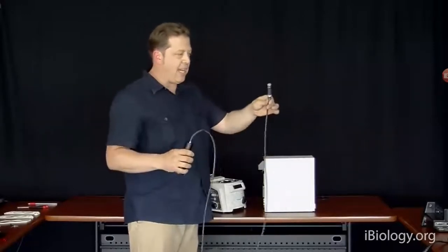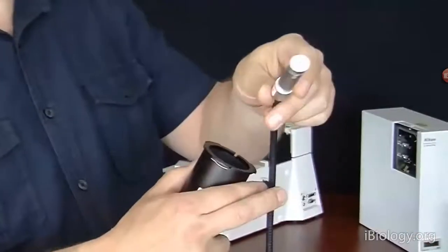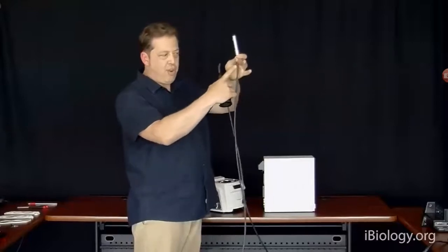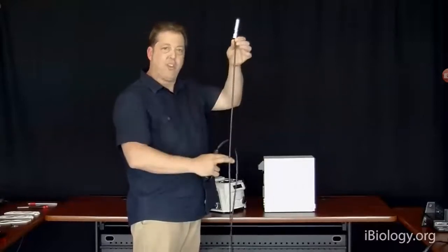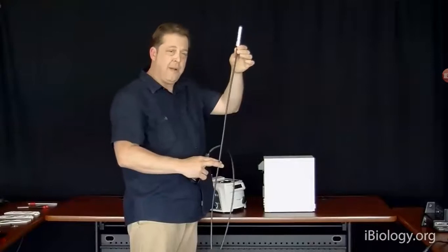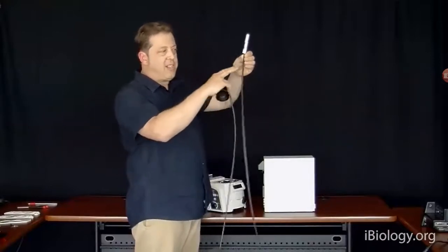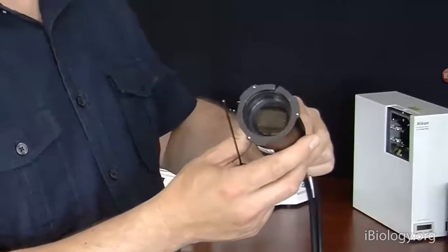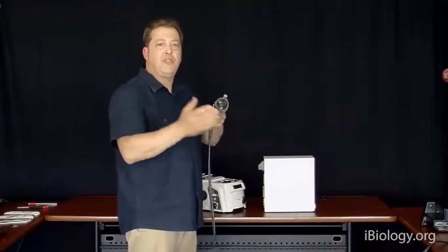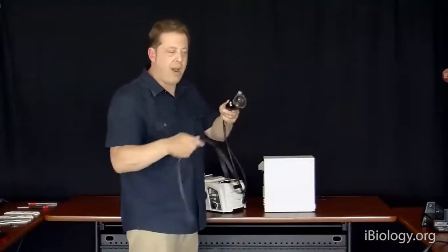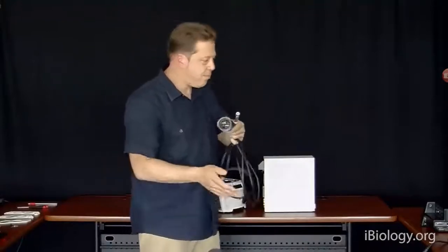And all the light goes in through what's called a liquid light guide. So the light coming into this aperture is actually trapped through total internal reflection in a core filled with liquid. I believe in this case, it's water that would keep the light based on total internal reflection within that core of water into this collimating lens, which is matched to the optics in the microscope and puts a large collimated beam of light into the microscope for epifluorescence illumination.